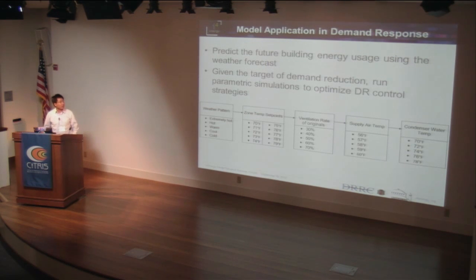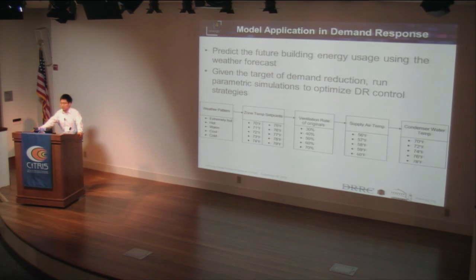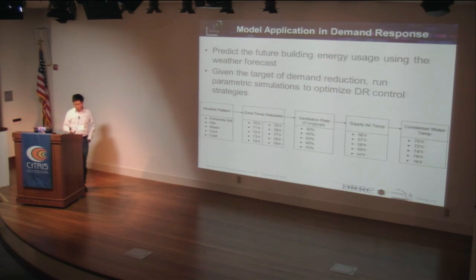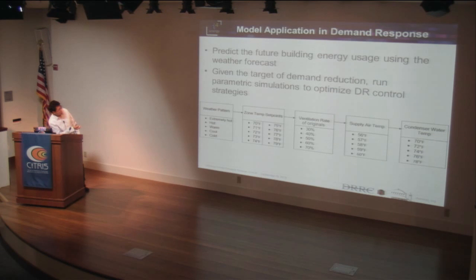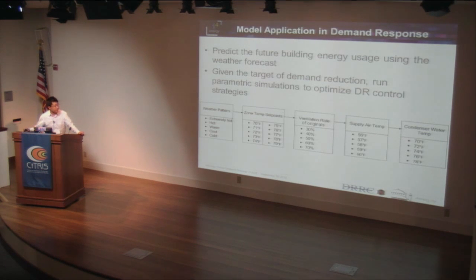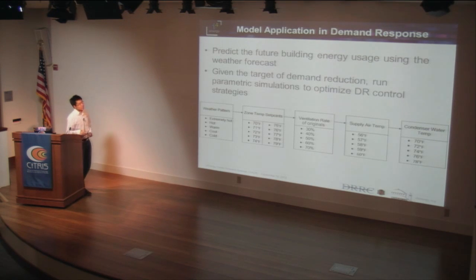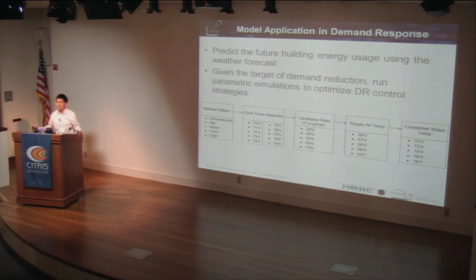Once we finish the model calibration work, we use the model to predict future building energy usage using the weather forecast from the Smart Air box. Given the target of demand reduction, we run parametric simulations to optimize the demand response control strategies. The parameters include weather patterns, zone temperature set point, ventilation rate, supply air temperature, and condensing temperature. All these different parameters combine into a large matrix, and the simulation model runs those different combinations to find the optimal control strategies to achieve our target.